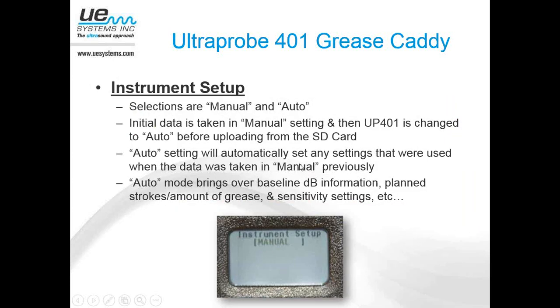Okay, instrument setup. Similar to the 10 and the 15, we have manual and we have automatic. So you're going to take the initial data in the manual setting. With the manual setting, we're going to be changing sensitivity. In some cases, we may even need to change the frequency that we're using. But we're going to be changing some of the ways that we're storing that data. So the next time, before you load that route into the instrument again, you would simply set the instrument setup to automatic. When you load that route in there, it's going to automatically set the sensitivity that was used. It's automatically going to set the frequency that was used. And then, probably most importantly, it's going to bring over that baseline information. So it'll bring over the baseline dB. It'll bring over the planned number of strokes. It'll bring over, again, any sensitivity settings.